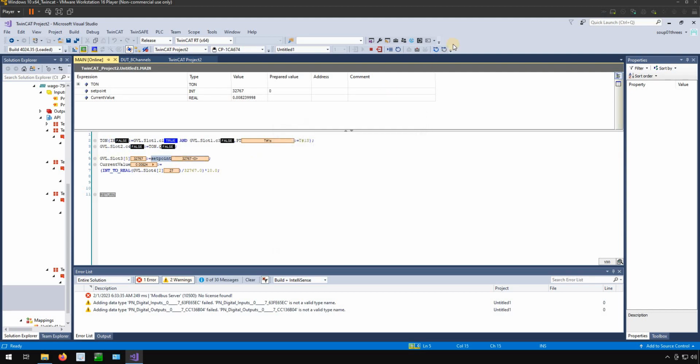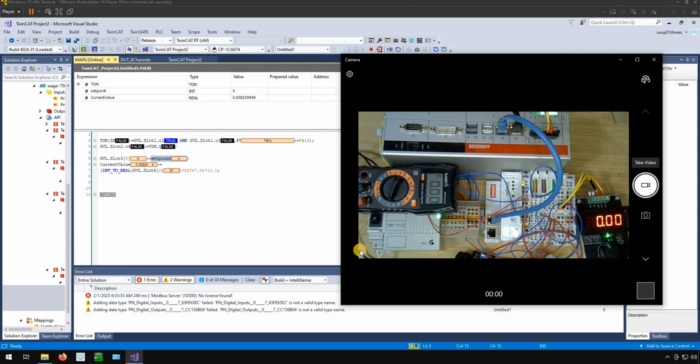Okay. Finally, we can check the analog input. So what we can do in here is, sorry, we use this raw voltage. You can see now it's around 1.1V. The scaling is correct. Let's do it. Now it's around 5.4 something. Okay, the communication is okay.